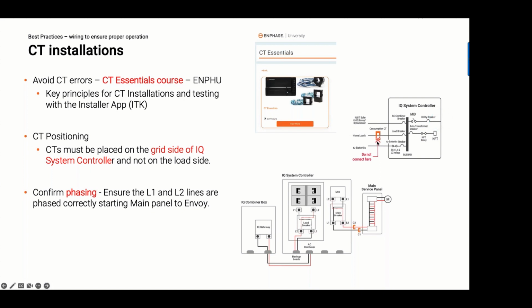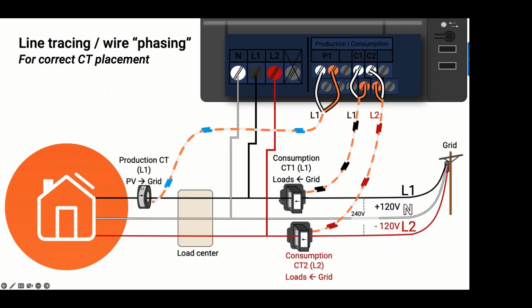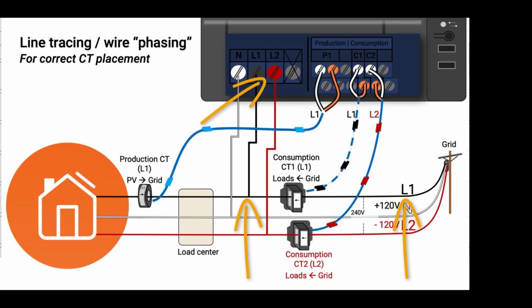So you need to ensure that the consumption CTs are installed on the line side of the system controller. A third common error found in metering of systems is related to misphasing of the voltage and current measurements of the system. This means the current and voltage measurements are coming from different phases. We can see it more clearly in this picture. The drawing shows that line 1 from the grid is feeding the IQ gateway line 1 power. This connection is also how the gateway gets its line 1 voltage measurement for metering. We also see the line 1 CT on the same line 1 voltage wire. The CT is connected into the line 1 CT port of the IQ gateway, which is how we get the current measurement for line 1.